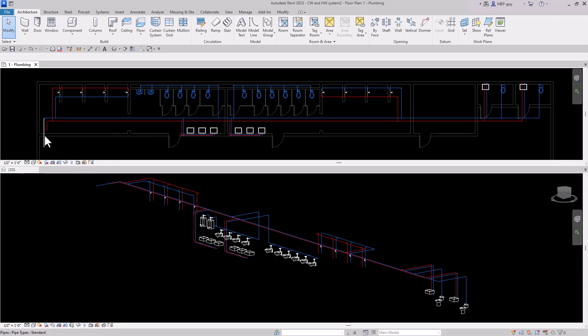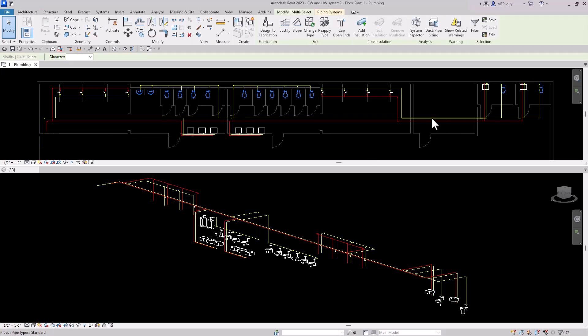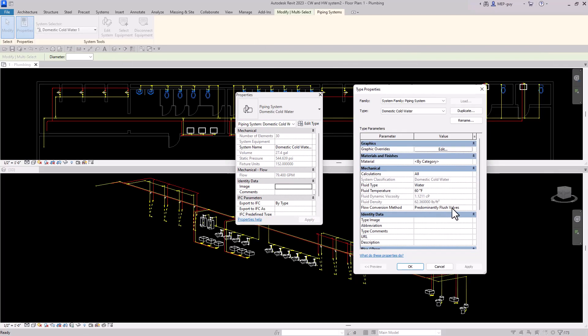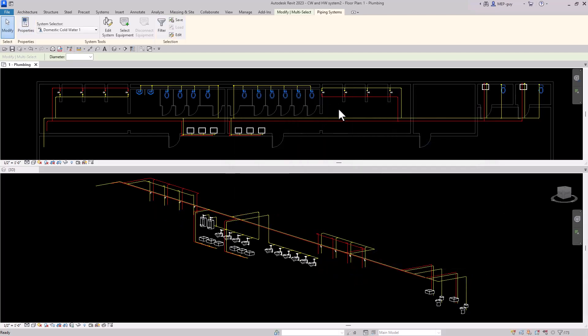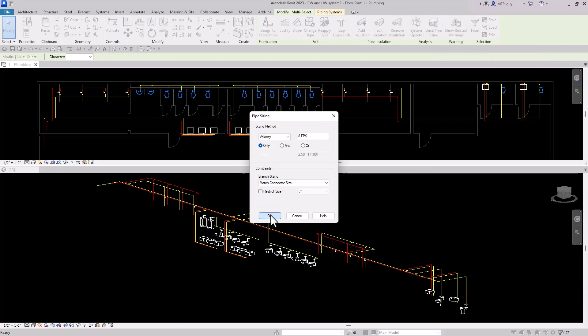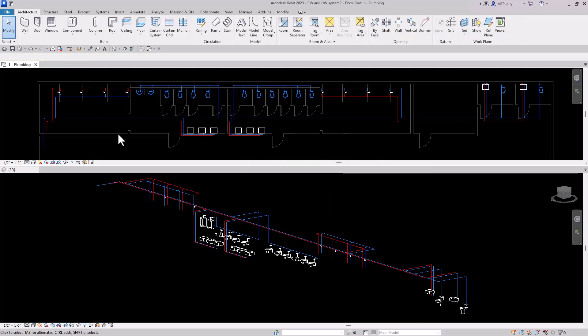We've essentially finished our plumbing design for the domestic water systems for this entire model. The last thing we have to do is size all of our piping - I can easily tab into all the pipes right here. First we want to make sure the sizing techniques are correct. I'm going to go into the piping systems button, go to edit type, and make sure that flush valves is selected for the flow conversion method. It is, so I'll hit OK, then I can quickly size this. I'm going to go back here and use the duct pipe sizing tool - we're going to match the connector size and size it for 8 feet per second. Hit OK.